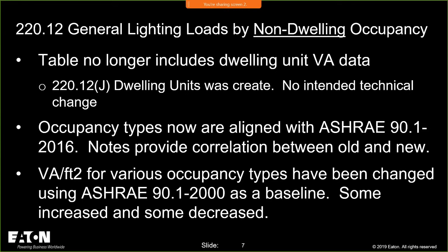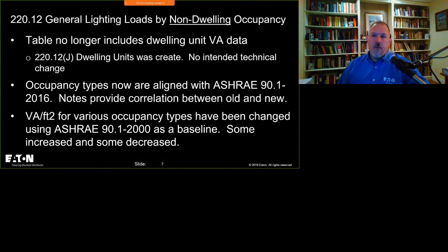But in any case, the focus was on the fact that a lot of our lighting is moving to LEDs and the lower energy profiles, which has to impact our load calculations in some manner. So if you'll notice that we looked at ASHRAE 90.1-2016, and you might say, why did you reference 90.1 2016? Because we don't have ASHRAE's on a much later version than that.